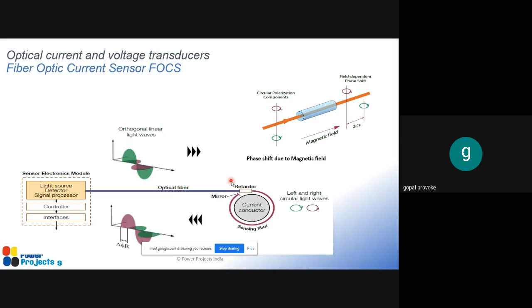So this is a conventional current transformer for 245 kV. See the size of the modern day fiber optic current sensor is reduced when compared to the previous one. And whenever we go for a higher voltage, for example 245 kV, and further higher voltage like 800 kV, the size is almost reduced to half.